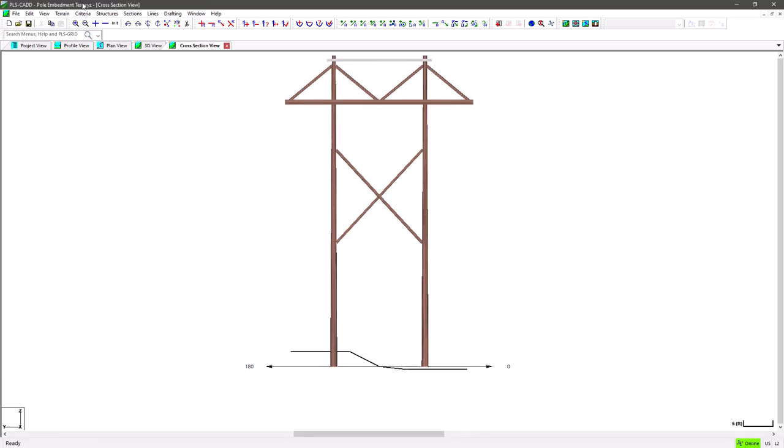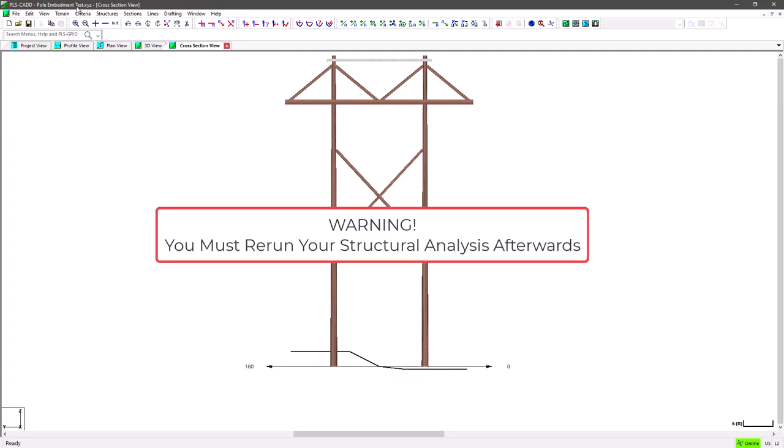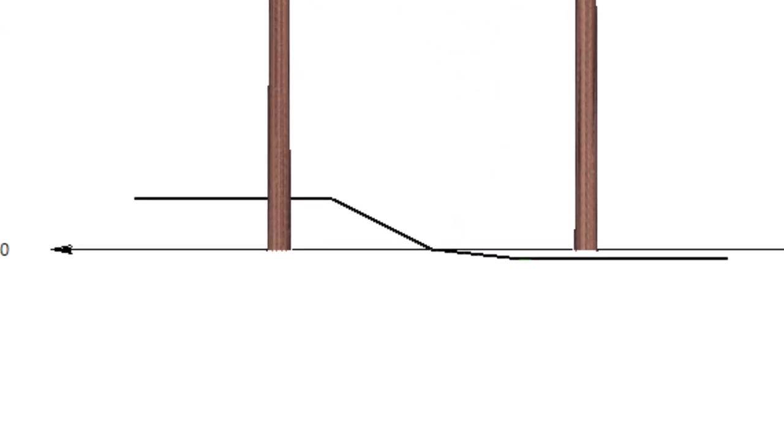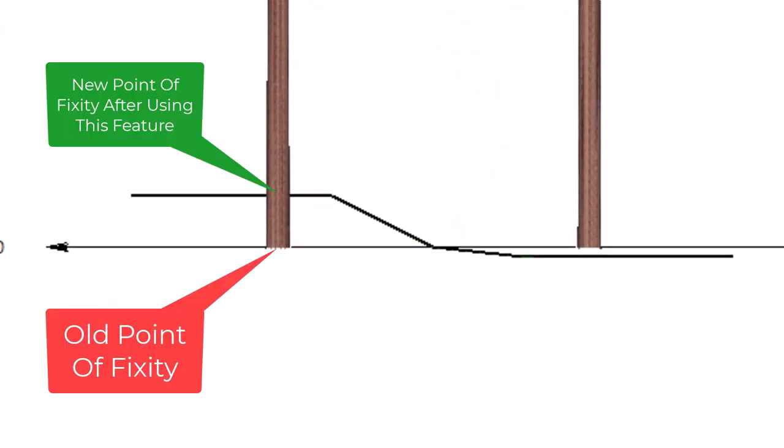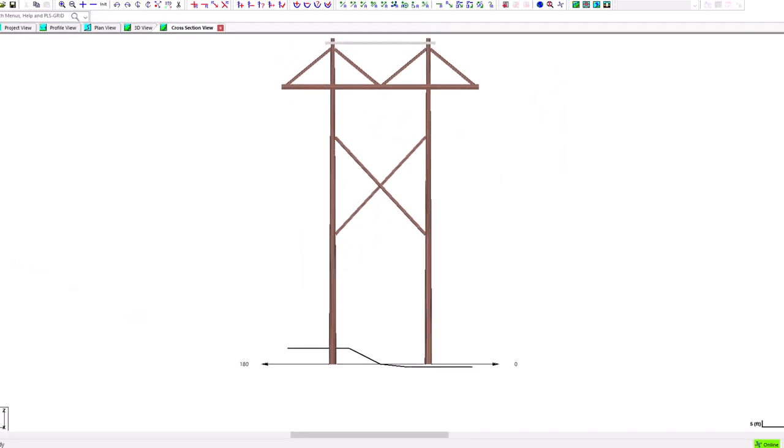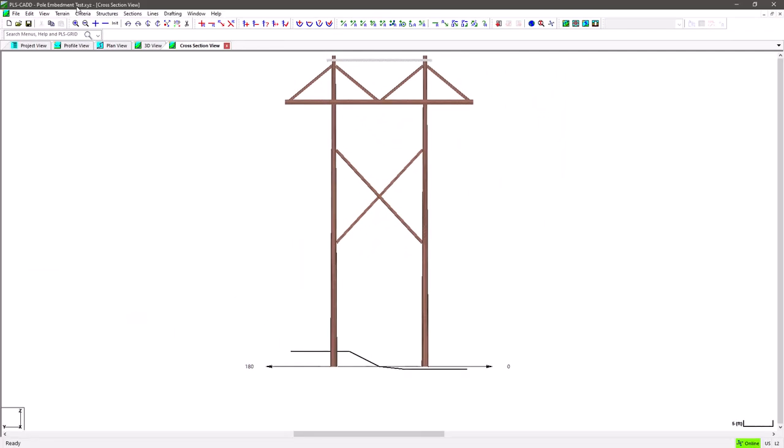So now let's take a look at how this feature can work on this structure and customize it to properly fit the tin surface. Also, please note that anytime you use this feature, you always have to go back and reanalyze the structure to ensure it's structurally adequate after the modification. Because the point of fixity changes and the above ground pole length in the PLS pole model changes, it will impact how the load flows through the structure which will ultimately impact its usage.